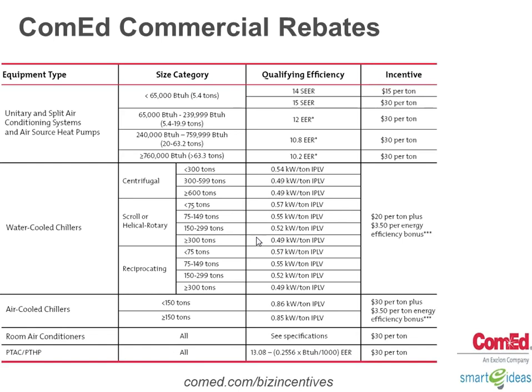So switching back over to ComEd on the electric side, if you have a water-cooled chiller, you look and see whether you have a centrifugal, a scroll, or a reciprocating compressor. If you have a screw machine, that goes under the scroll/rotary compressor scenario. So you look and see, what type of compressor do I have? What size unit do I have? And then what's my kW per ton target? It's a little bit different for each one depending on the class of the machine, because all those different classes of machine have different code baselines. Therefore the rebates differ for each one of those types.